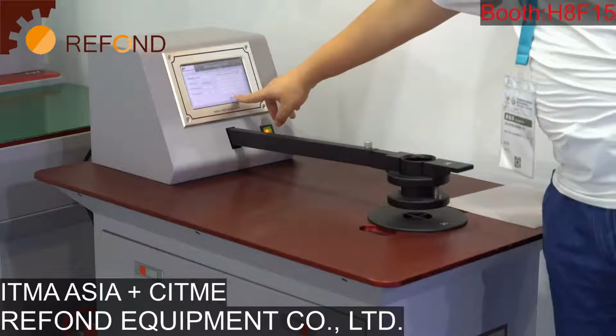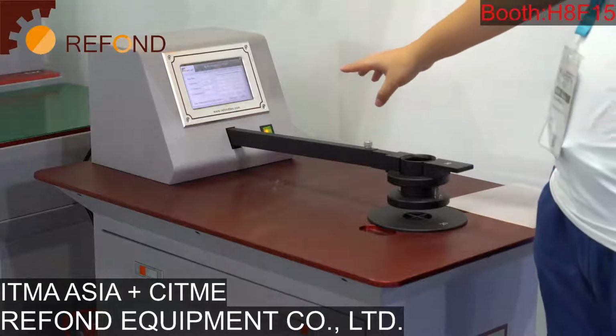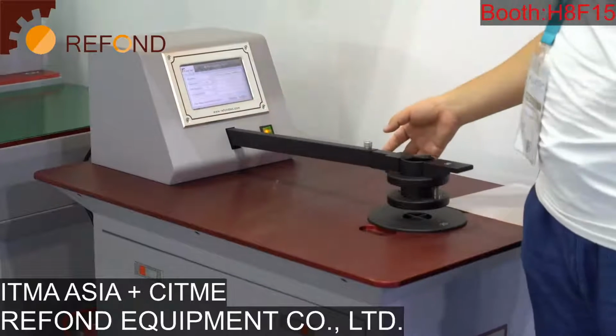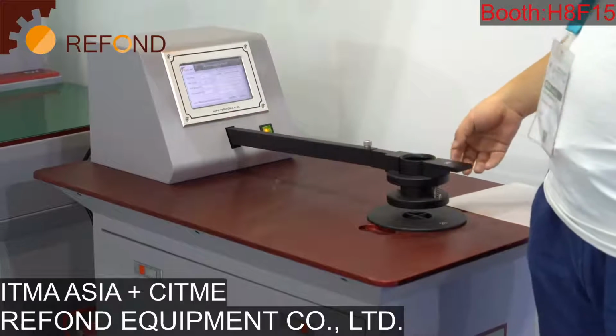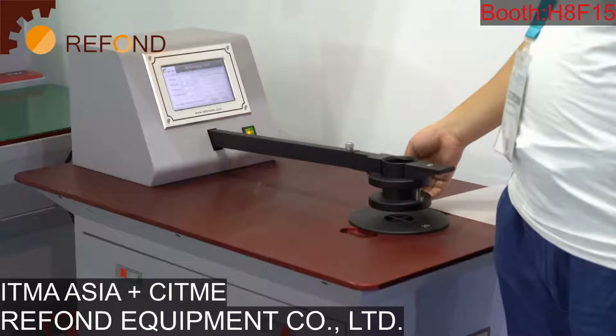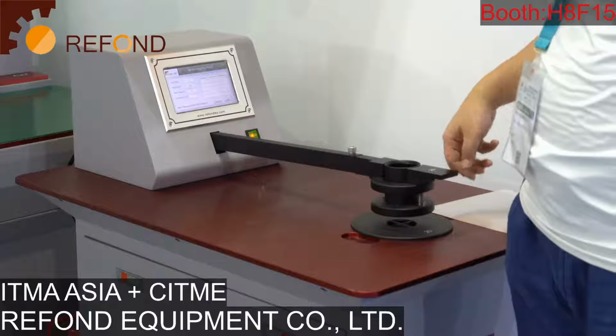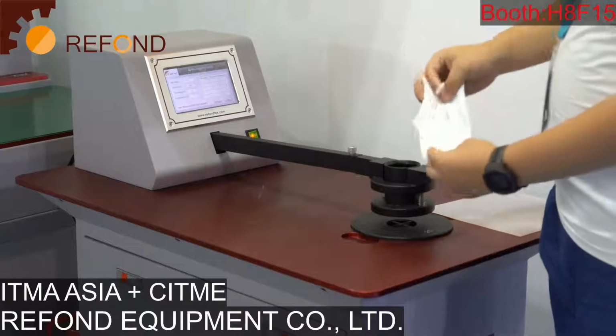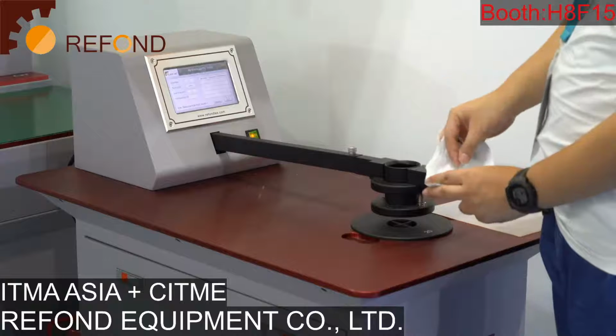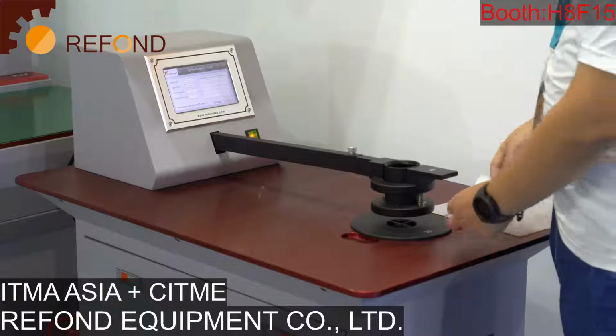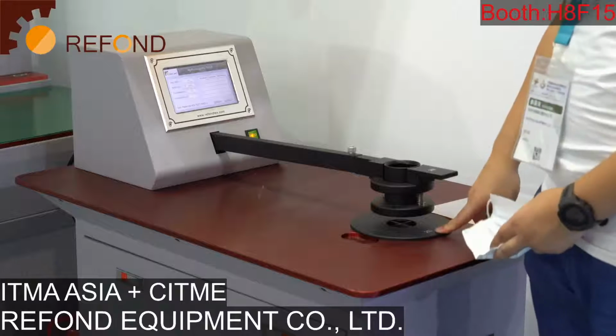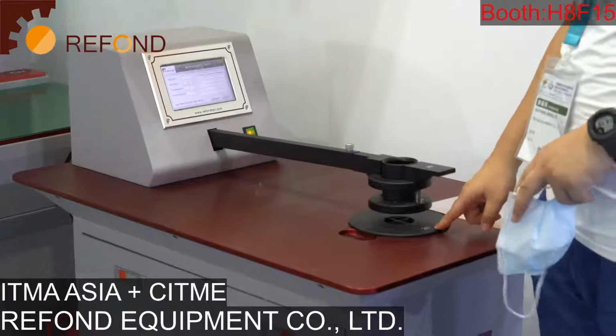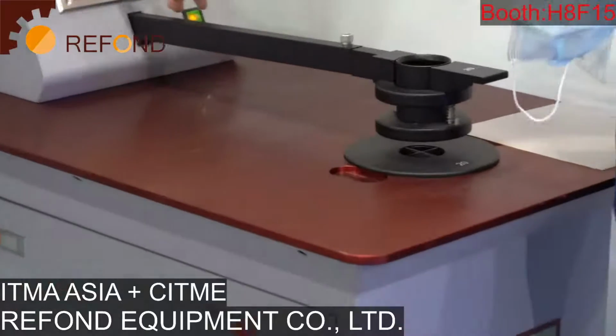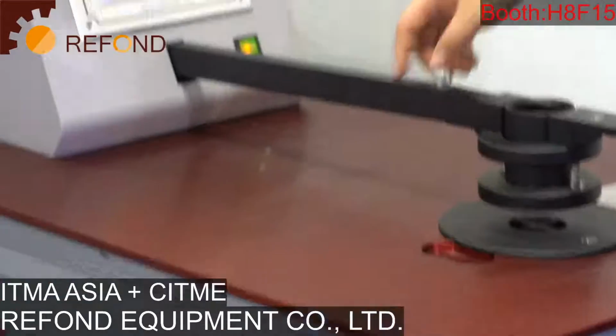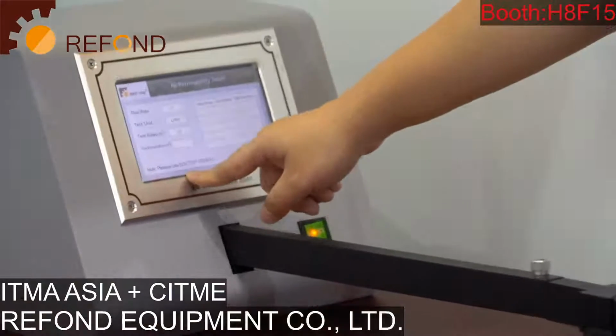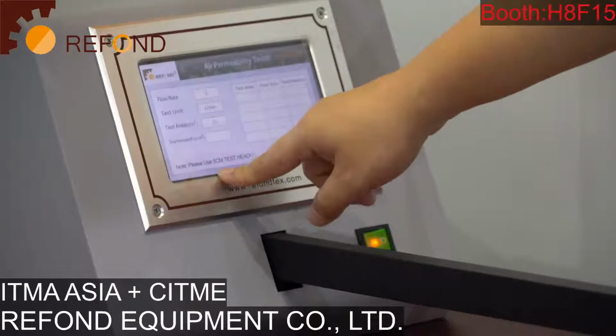For the fixed flow rate test, we added it for the measurement of the breathability of face masks. It's also called the flow resistance of the face mask. So it measures how difficult it is for the air to move through the face mask. For this test, you need to use the 5 centimeter squared test head. We have a reminder up here on the touch screen, for reminding the user.